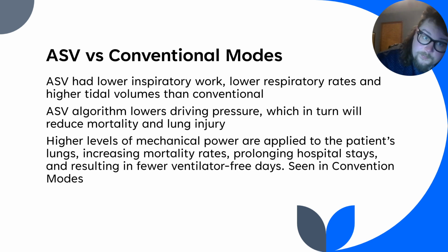So the ASV uses lower inspiratory work, lower respiratory rates and higher tidal volumes than the conventional modes. This algorithm lowers the driving pressures, which then ultimately reduces lung injury and mortality.